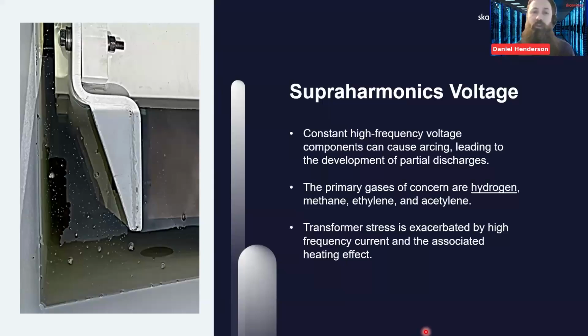And normally your protection, like you say, where it either hasn't got a conservator and you're doing your standard DGA and you've got temperature and overpressure protection, or where you have got a Buchholz relay, that's really there for oil leaks or a significant event like a major arc inside your transformer. Then you get the bubble going up to your conservator and tripping your Buchholz relay. And on smaller transformers, you might have an integrated dissolved gas and pressure, temperature transducer, which looks at this. And again, it's so common that these do trip on solar sites. Very common. And it's the accepted thing because of the nature of the network. I just find it interesting because it's not the accepted norm as an electrical engineer from other industries. And so we need to understand a bit more about the impact of these superharmonic components.